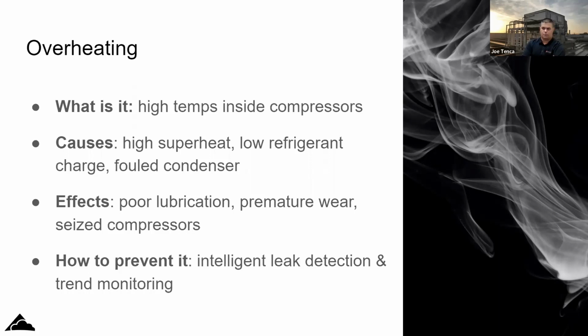There's a lot of, put my gauges on and use my meter. I'm not saying don't do that, but I think there's a lot of information we found in the computer system to see what it's doing. And it's what controls it. So if a transducer's off, then the controller can't control the compressors properly anyway. So you use it to see what's going on, but you also have to use it to verify that it's controlling properly.